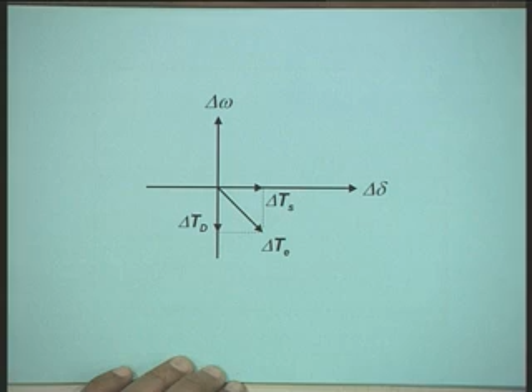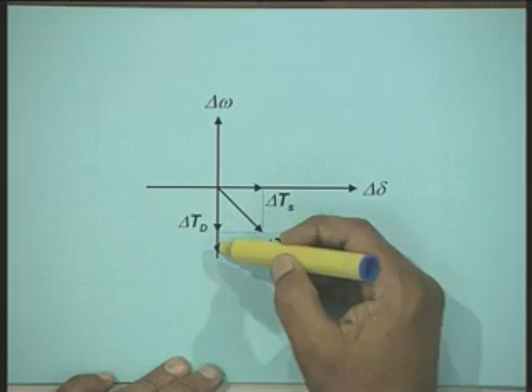Now, the component of the air gap torque in phase with speed deviation comes out to be negative, that is, the power system stabilizer will contribute a negative damping torque, and if this negative damping torque is more than the normally existing system damping, then it will cause excitation of the torsional modes, because as we have seen, the damping of the torsional modes is very low. The moment you have a large negative damping torque produced due to the power system stabilizer, the net damping may become negative and the torsional oscillations may grow in magnitude, and therefore, there is a necessity to account for this adverse effect when we design our system.